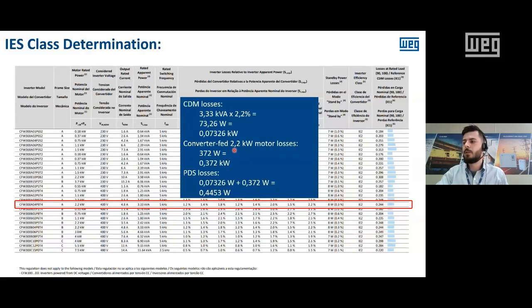The motor losses should be defined by the manufacturer. Here I took a reference motor from WEG, and the losses were defined as 372 watts. And then if we sum both values, we are going to have in total 0.4453 kilowatts. This is kilowatts, I forgot the K.